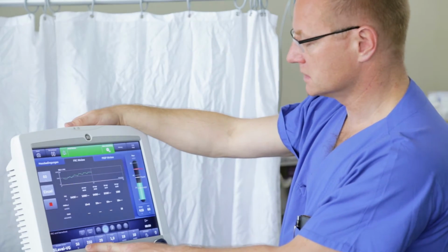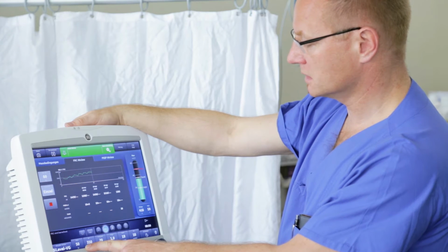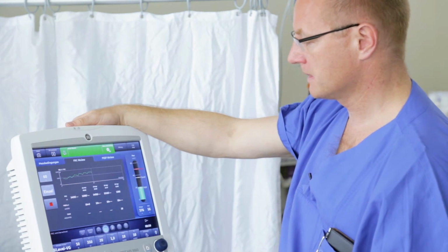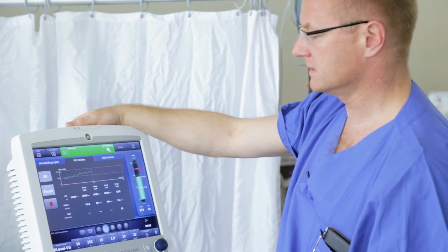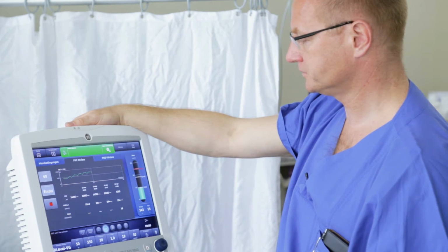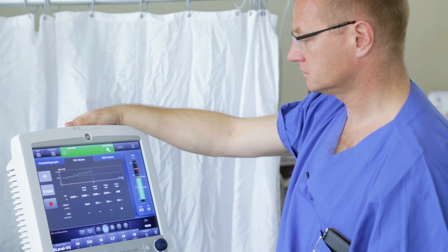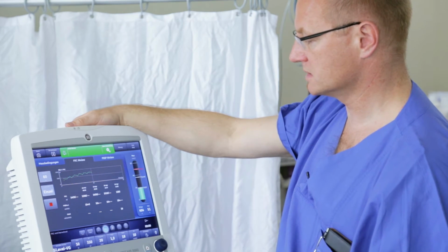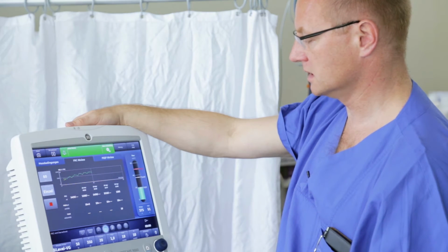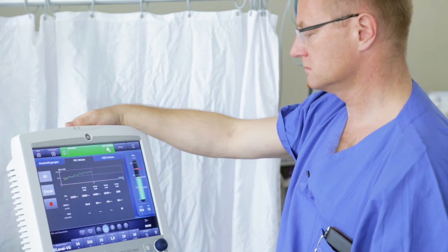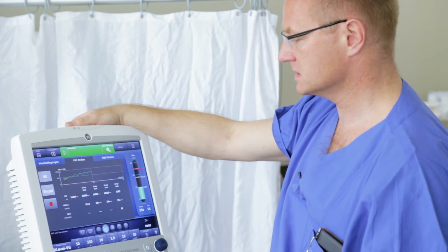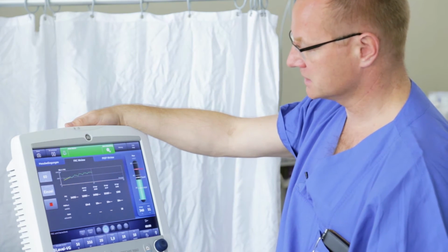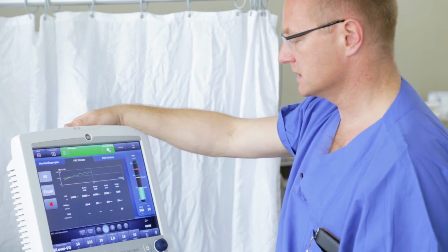The inspiratory oxygen concentration has now declined from 60% back to 50%, and the second measurement has begun within a few breaths. And here we are already seeing the first value of the second measurement as a yellow dot. It will now be another 20 to 25 breaths before the inspiratory oxygen concentration is readjusted and the second measured value is read out.